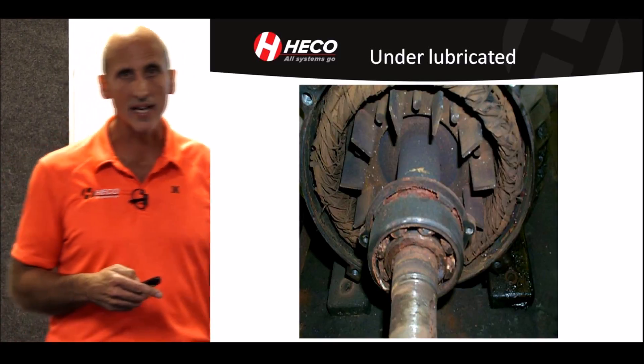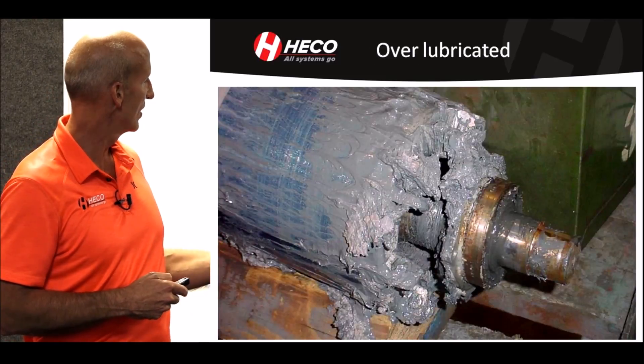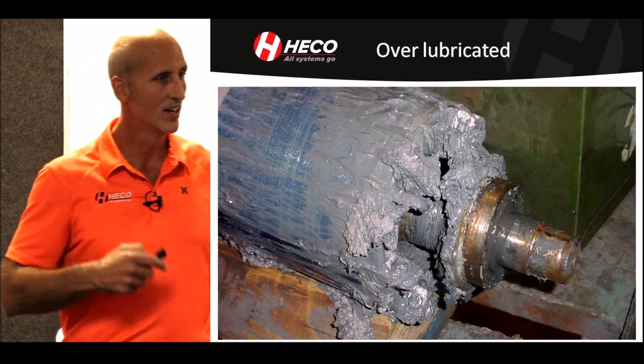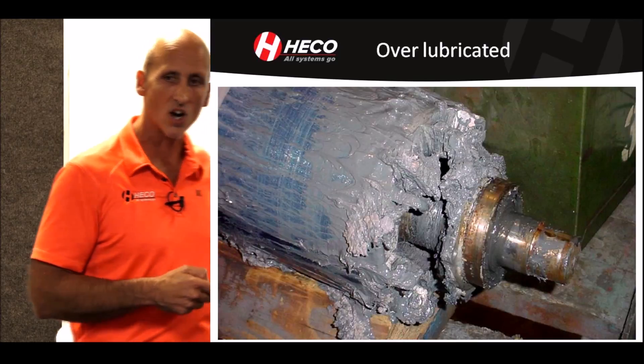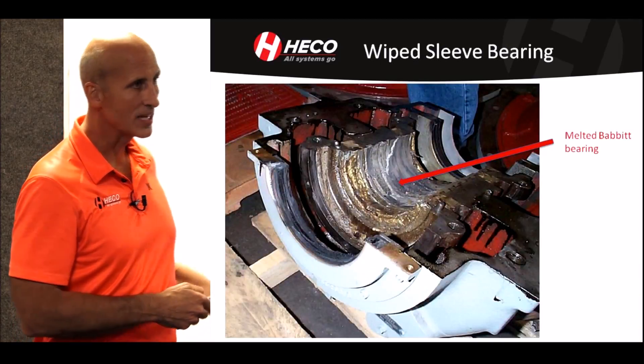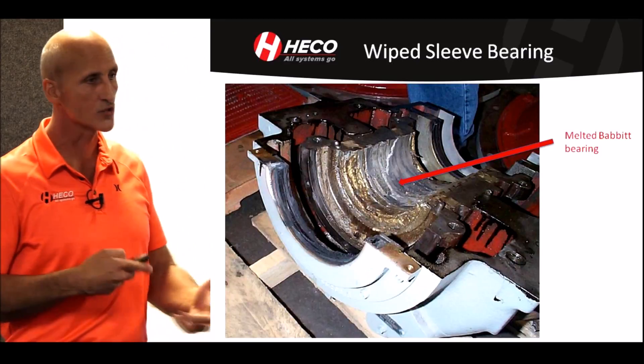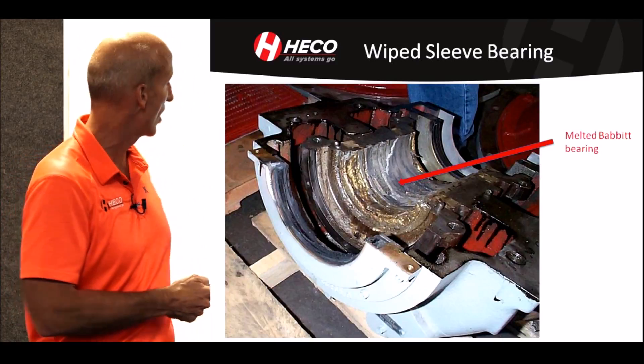Here's an example of an under-lubricated machine — you can see how hot and how dry it is. And we also very commonly still see over-lubrication, where that person was really good at lubricating but lubricated so much that he caused damage in the other direction. Here's a wiped sleeve bearing showing an example of a sleeve bearing failure, which can be caused from contamination in the oil, among other things.